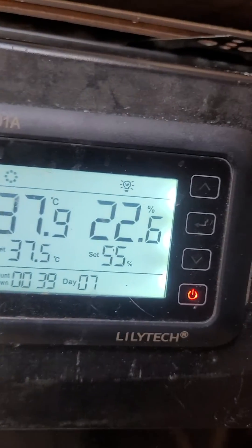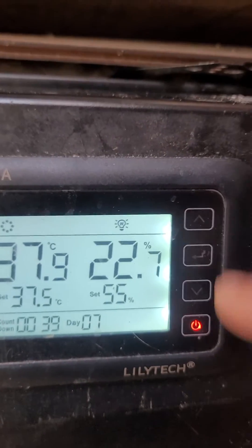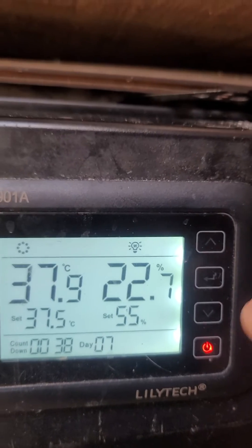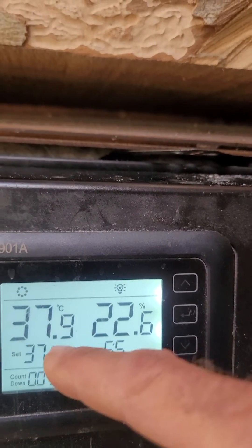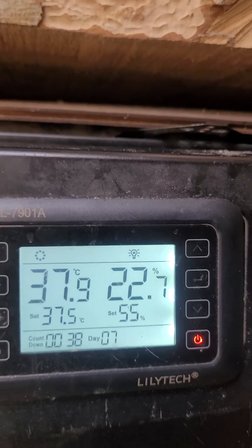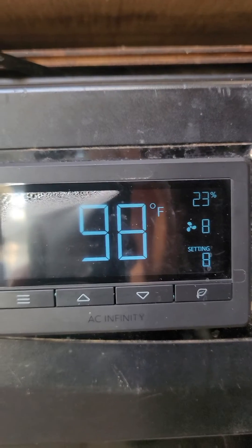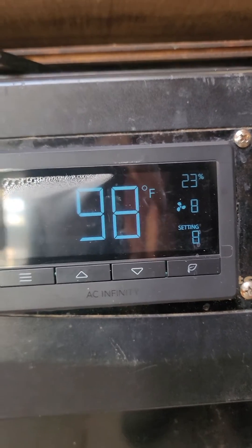After you don't touch anything for a couple of minutes, it'll set. Once you put in the change by going up and down — doing a minus 0.9, or minus 0.8, or whatever you need — to get it adjusted properly, then you push the enter button and that saves it. This other controller is for a circulation fan — a blower fan from a fireplace that I've positioned in the back of the unit to circulate the air.